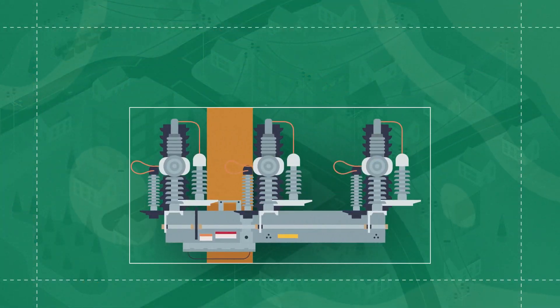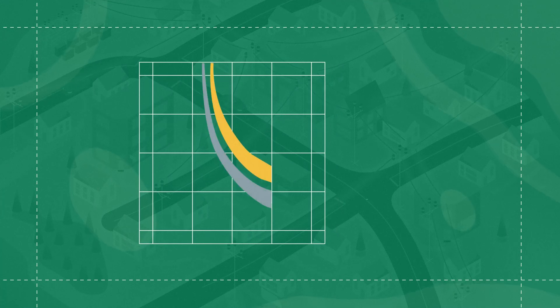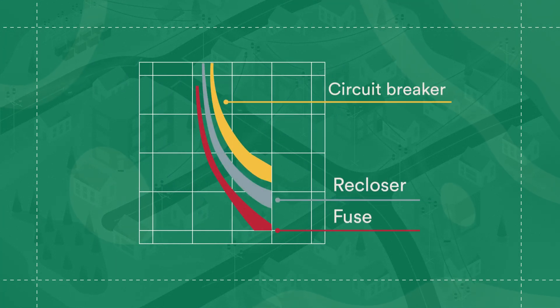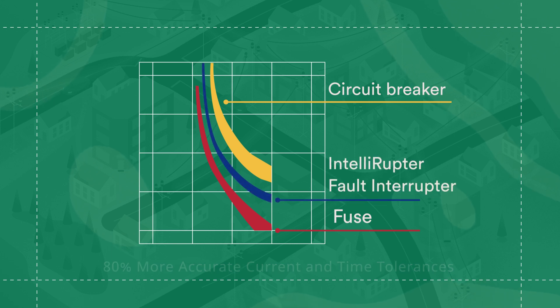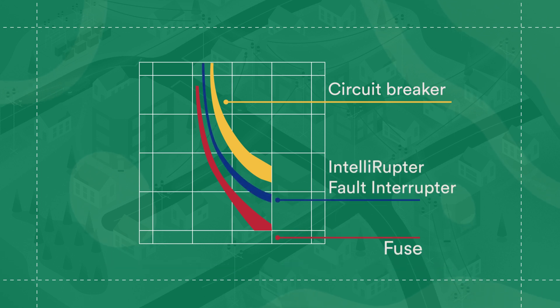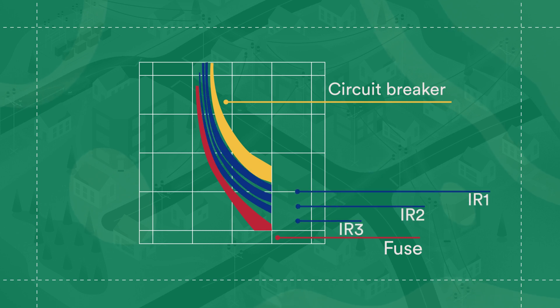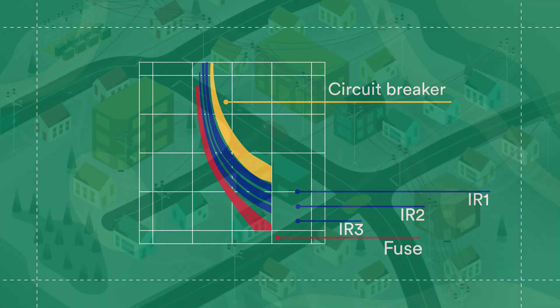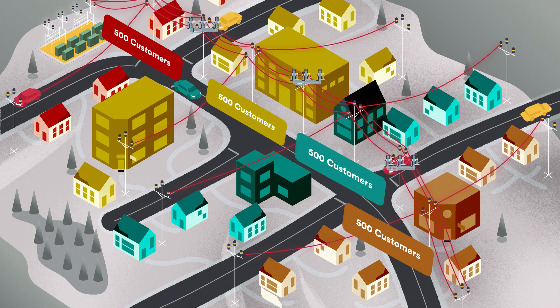Discover S&C's IntelliRupter PulseCloser Fault Interrupter. Using highly accurate sensors, IntelliRupter fault interrupters have 80% more accurate current and time tolerances than conventional reclosers. This heightened accuracy gives these devices skinny TCC curves, allowing three fully coordinated IntelliRupter devices to replace this single conventional recloser. This means you can further segment your lines — in this case, you can bring your 1,000 customer segments down to 500 per segment.